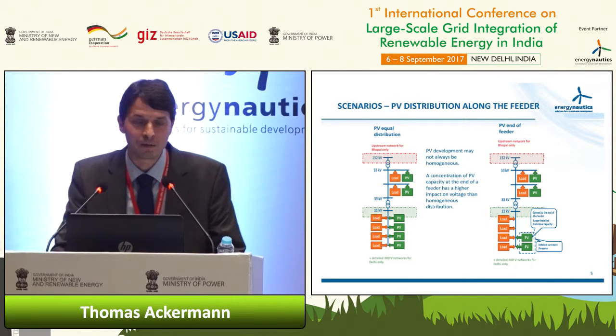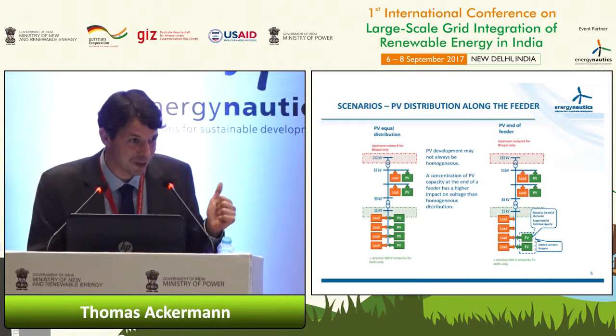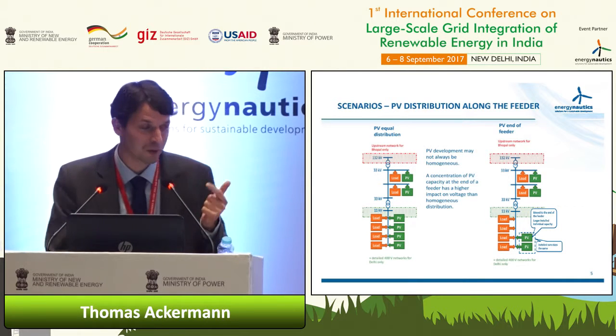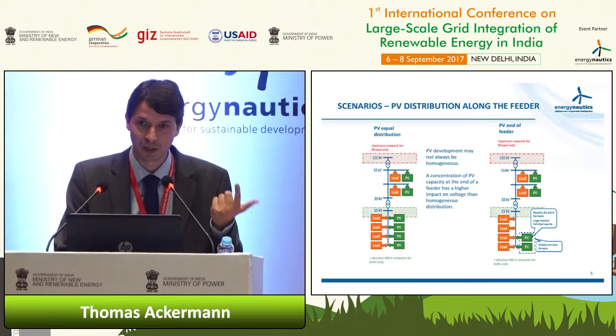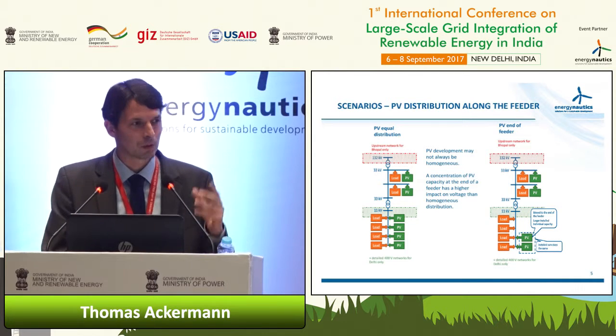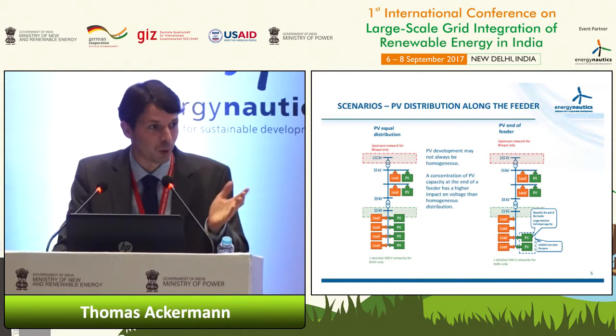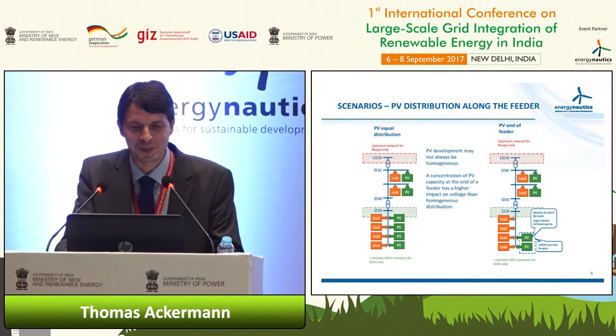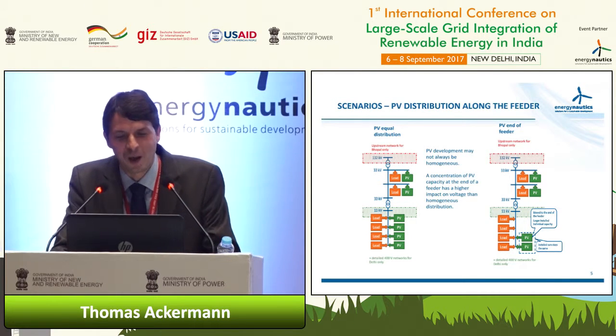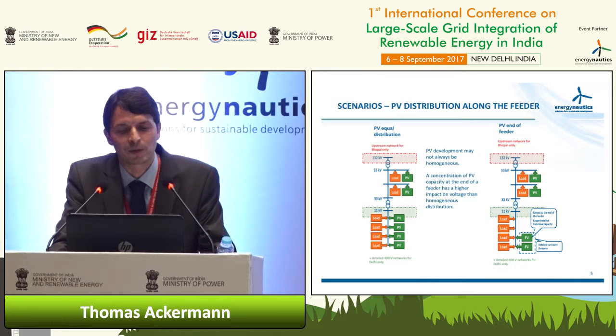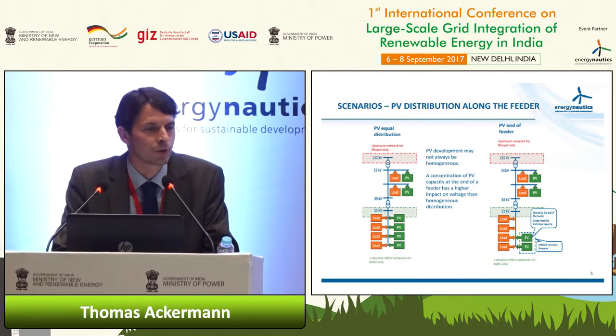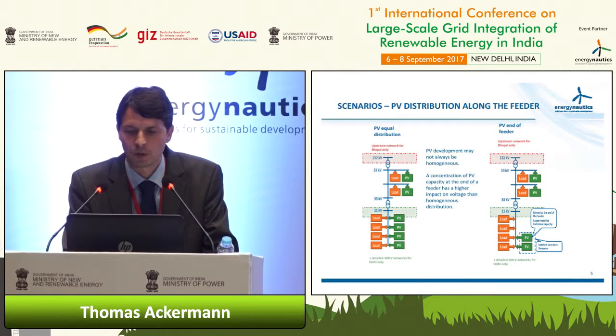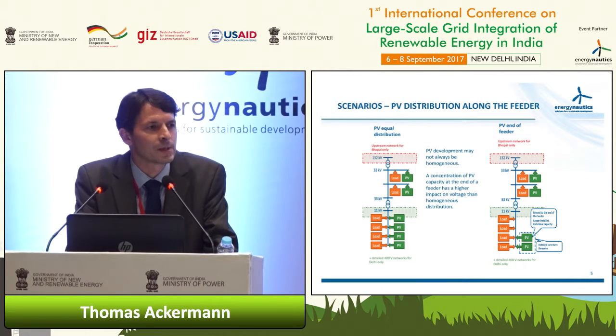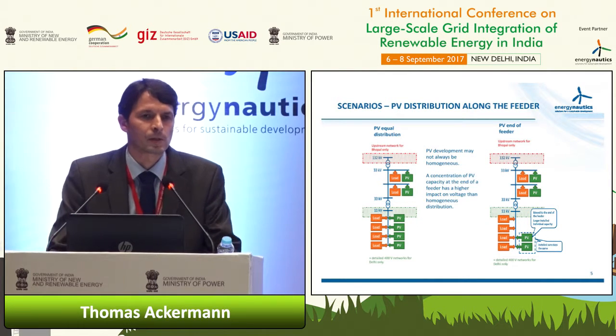We said it is, A, the inverter capacity of the PV system - in Germany it's quite common to take the PV peak capacity, the DC side, but we took the AC side because that's more common in India, as I've learned over the last couple of weeks and months. And secondly, it is rated to the distribution transformer size. If I jump back some slides - it's not shown here - the typical size in the urban area is 630 kVA.